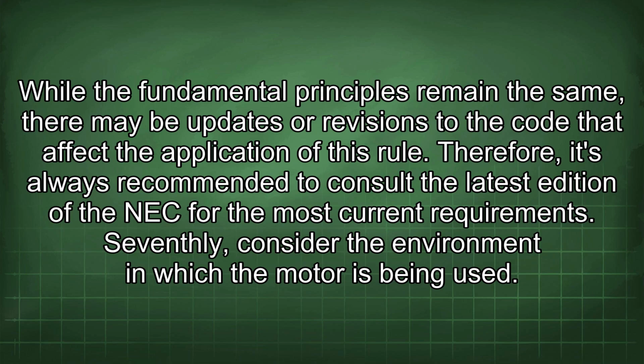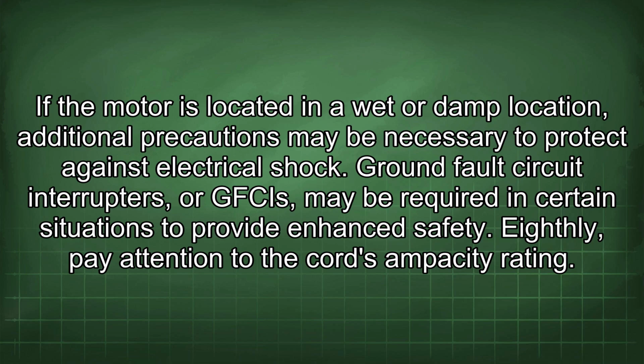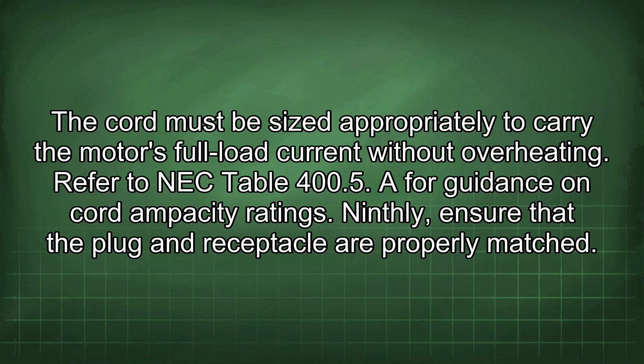Seventhly, consider the environment in which the motor is being used. If the motor is located in a wet or damp location, additional precautions may be necessary to protect against electrical shock. Ground fault circuit interrupters, or GFCIs, may be required in certain situations to provide enhanced safety. Eighthly, pay attention to the cord's ampacity rating. The cord must be sized appropriately to carry the motor's full load current without overheating. Refer to NEC Table 400.5 for guidance on cord ampacity ratings.